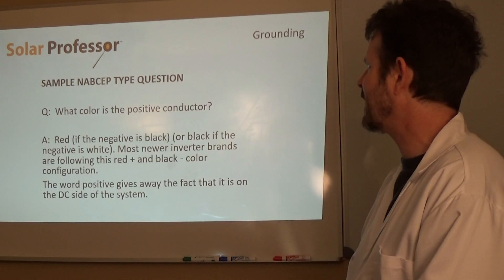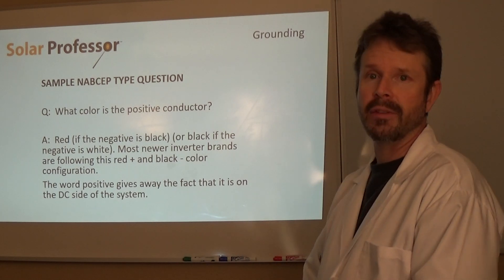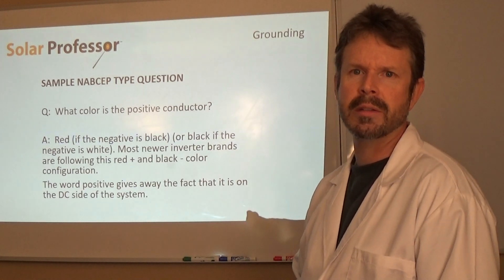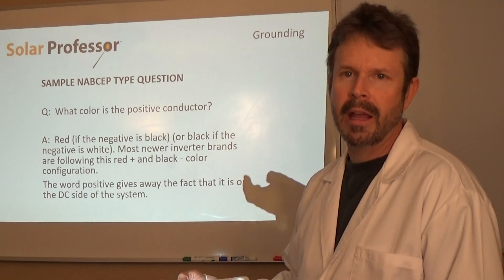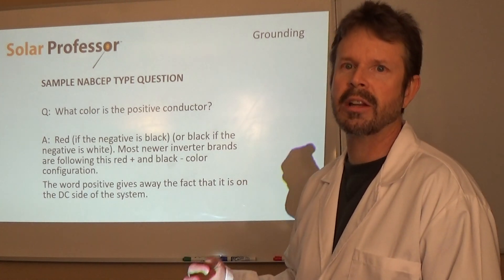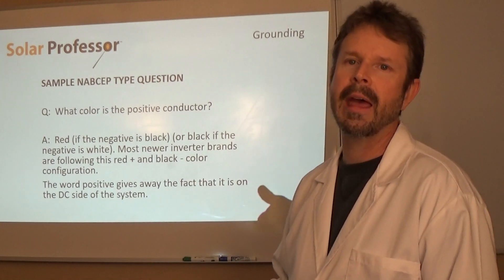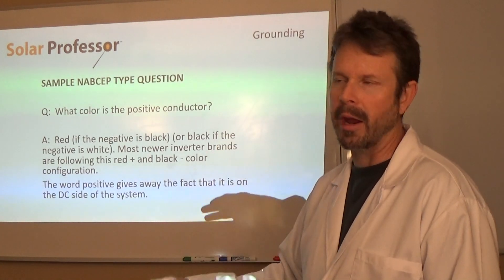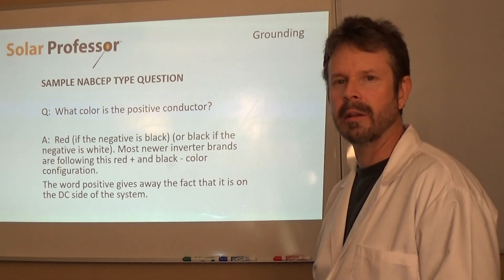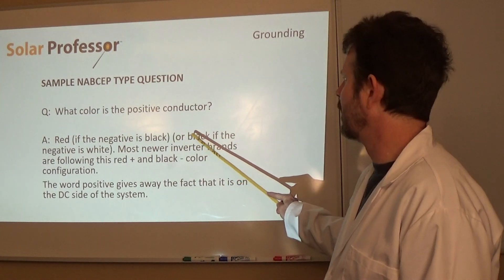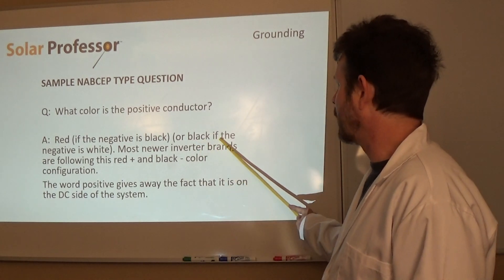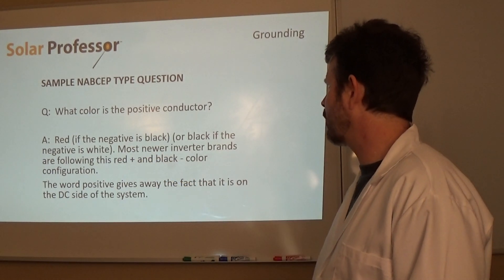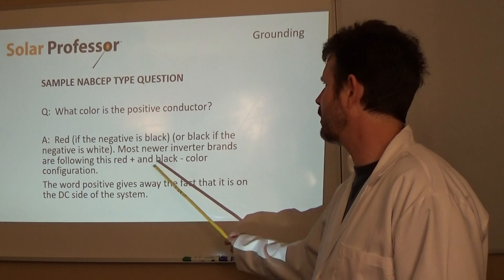Here's a sample NABCEP question: What color is the positive conductor? Well, the answer is red — and it's red if the negative is black. That's kind of like a car, right? Red is positive in a car system and black is negative. And in a car, the black is touching the frame, so that is a grounded conductor — part of the grounding situation in the car, which is the frame. If it's like the picture we just saw where black is positive, then the negative is white. You could end up in a situation with either. Most newer inverter brands are following red for positive and black for negative.